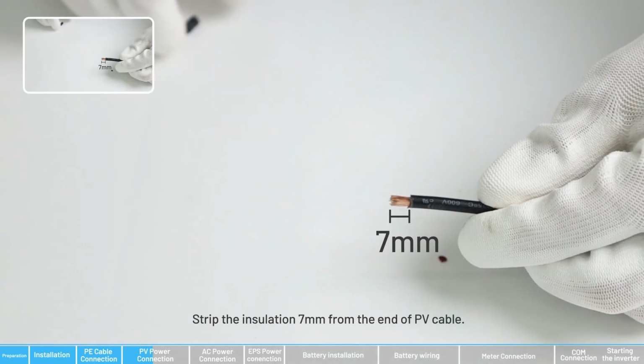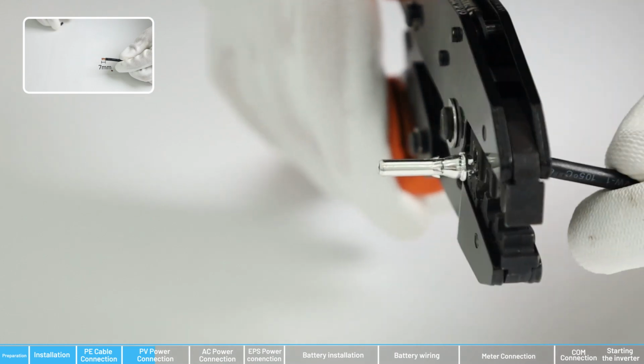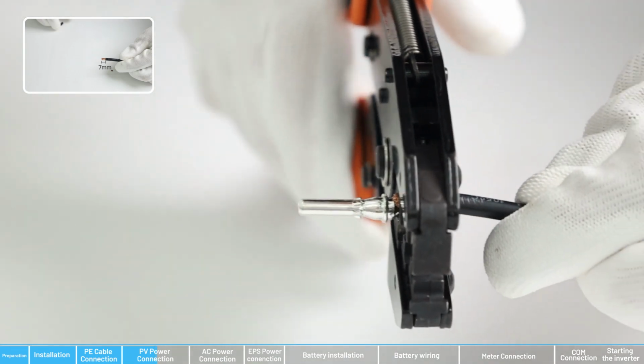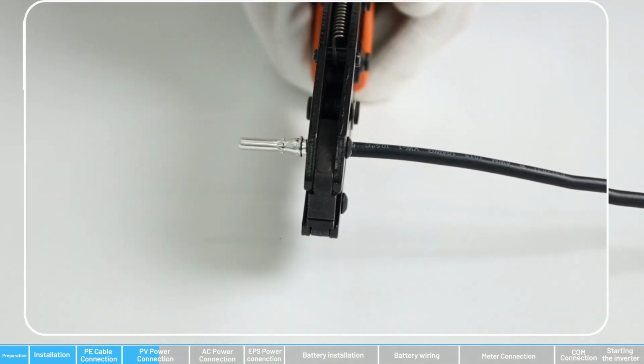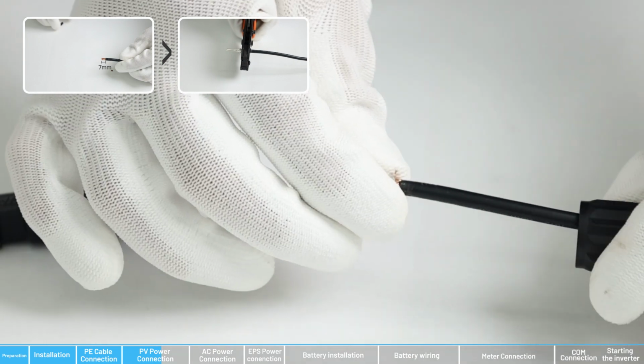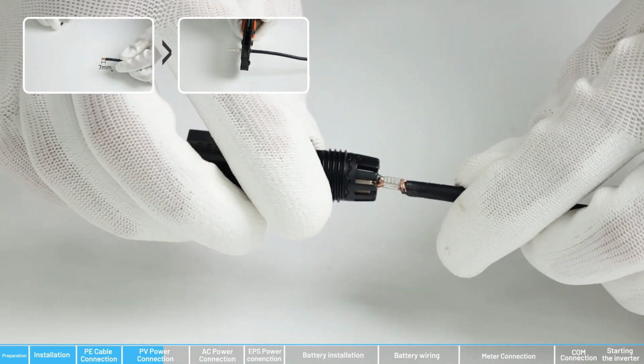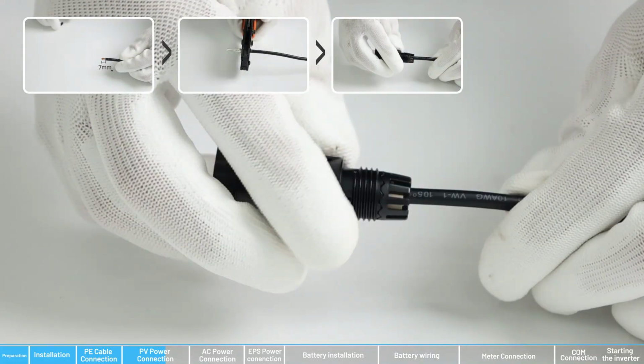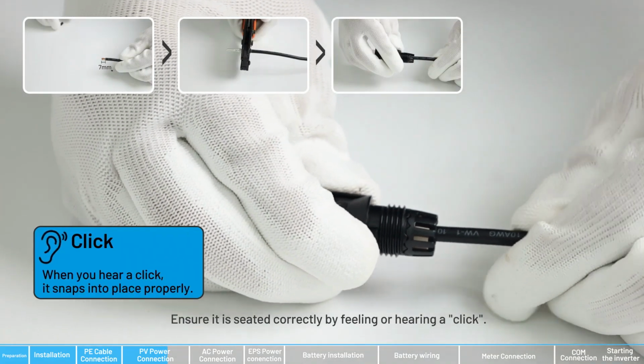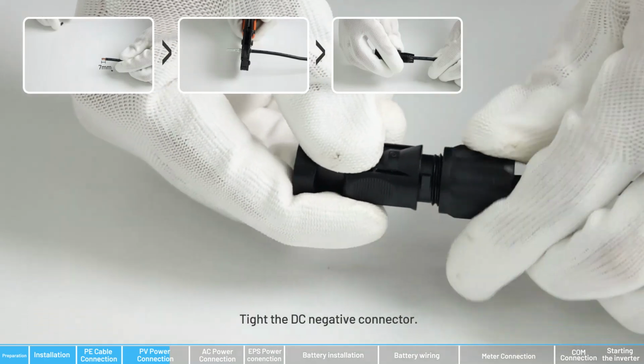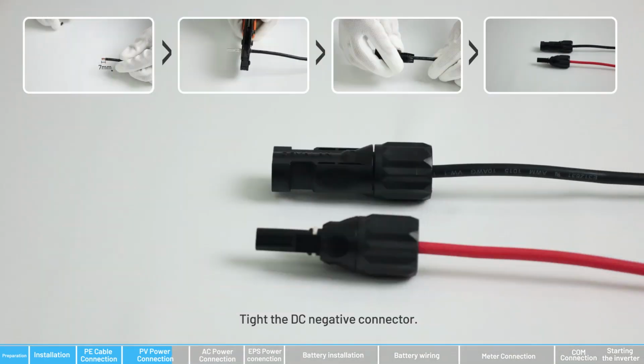Strip the insulation 7 mm from the end of PV cable. Crimp the PV cable. Ensure it is seated correctly by feeling or hearing a click. Tighten the DC negative connector.